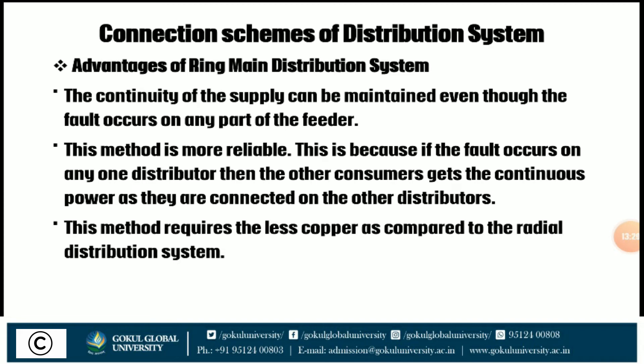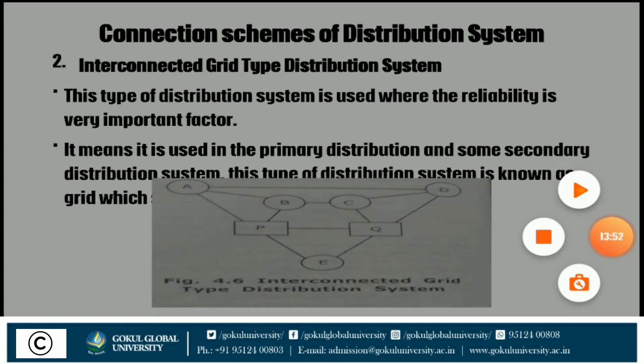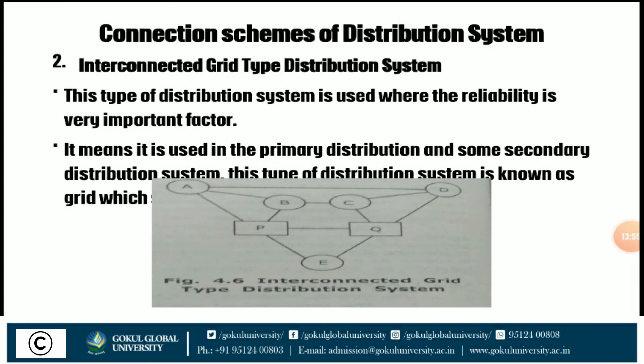Advantages of the ring main distribution system: continuity of supply can be maintained even if a fault occurs on any point of the feeder; this method is more reliable because if a fault occurs on one distributor, other consumers get continuous power from other distributors; and this method requires less copper compared to the radial distribution system. Third is the interconnected grid type distribution system, which is used where reliability is a very important factor — used for primary and some secondary distribution systems.